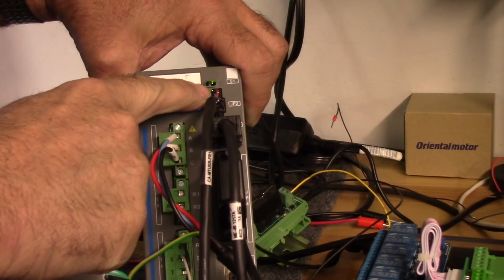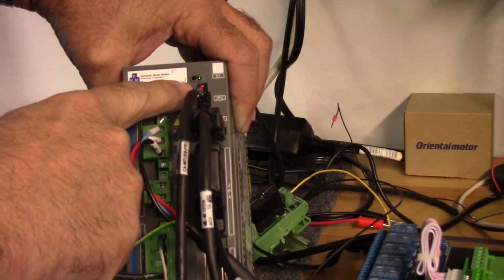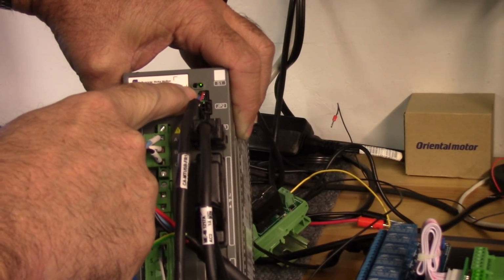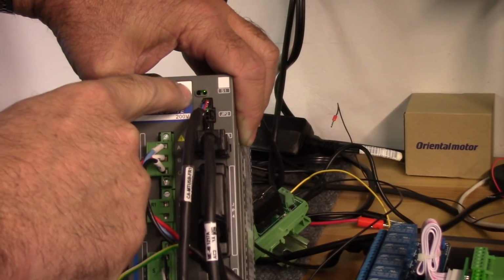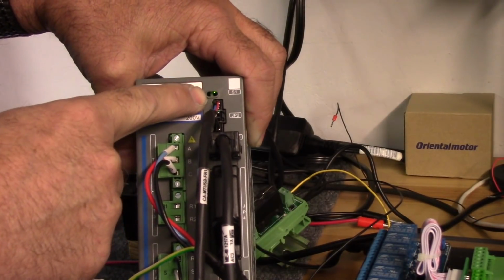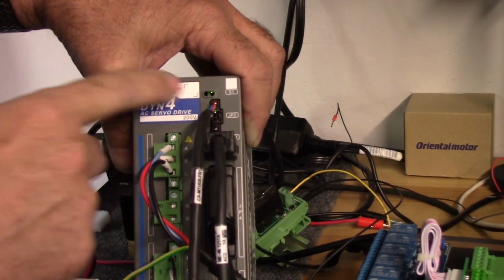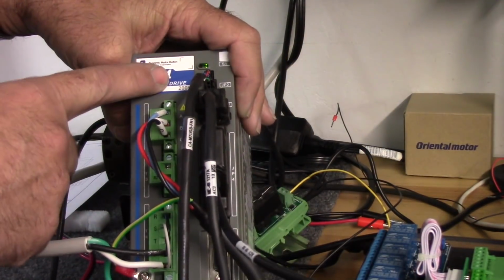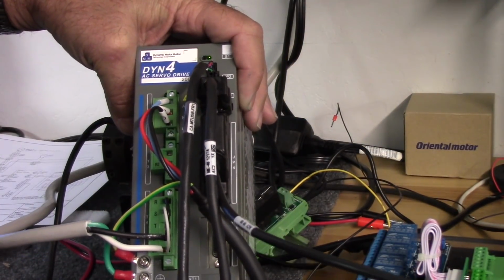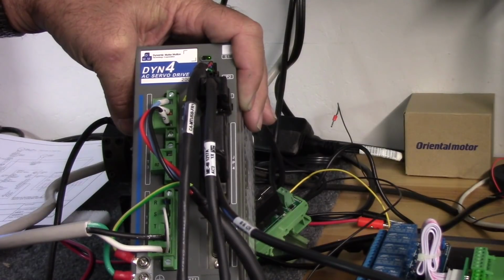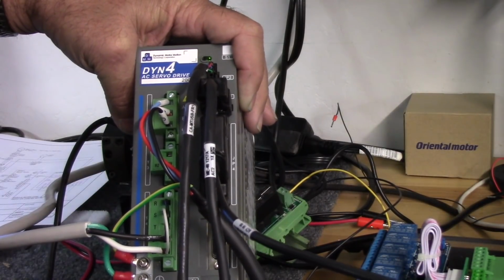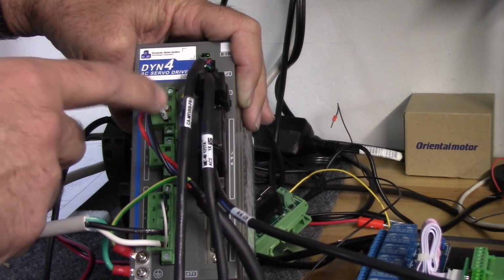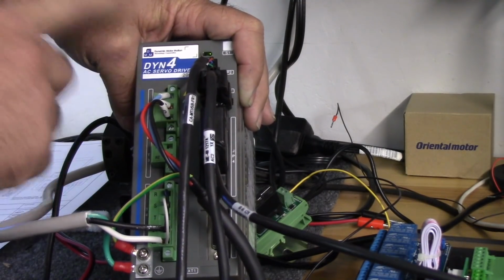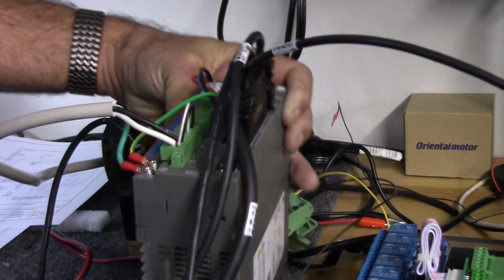Now, if you need to see which one is faulted, you open your cabinet and look at this LED right here. Not sure if you can see it, but this one is not faulted and it's in a green state, so it's good to go. If it's faulted, there'll be a flashing red LED in that window. So that would be your faulted drive. And to reset these drives, you have to remove power from them. How you set that up is up to you, whether you use an e-stop relay, which is the preferred method, or however, but you have to remove power from the drives to reset them. So keep that in mind.